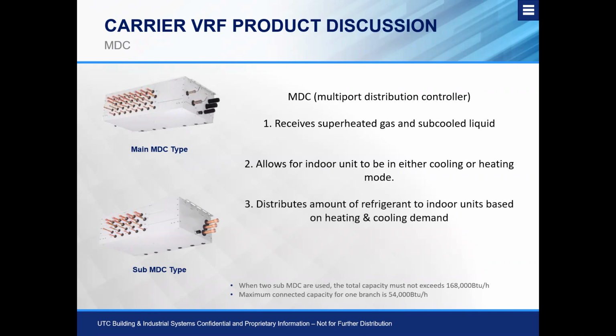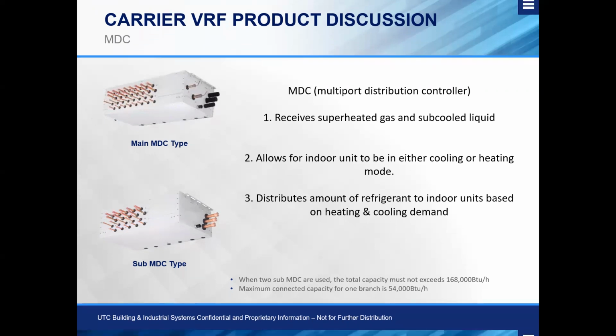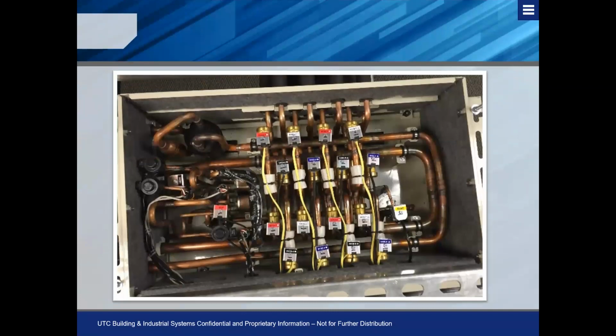And finally, it's going to distribute the amount of refrigerant via solenoid valves to the indoor units based on what they're calling for, whether it's heating, cooling, or a simultaneous heating and cooling. So you can see the top is completely removable, which means this box is serviceable. So the solenoid valves that you see there with the different red, white, black, and blue colors on there, if one of those for some odd reason would fail shut or fail open, you don't have to braze to replace that actual electrical coil.